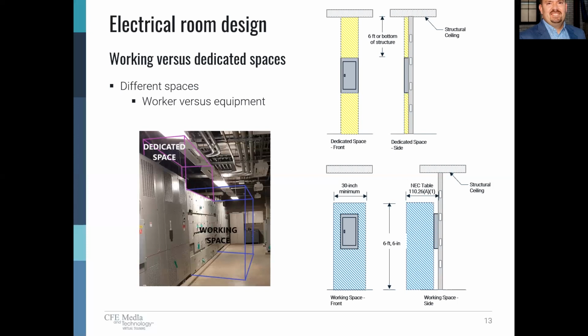So as we look at working clearance, the width required, the minimum width is 30 inches. But in the case of equipment that's larger, say we have a 6-foot wide switchboard lineup, the width of the equipment becomes the requirement. So 30 inches is the minimum. If the equipment is larger, the working clearance is required to be wider as well. As far as the depth of the working clearance for the equipment, it's contingent upon a couple of factors, and this requires references to tables in the NEC.